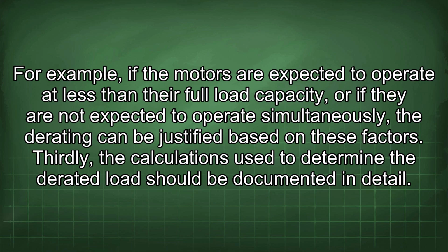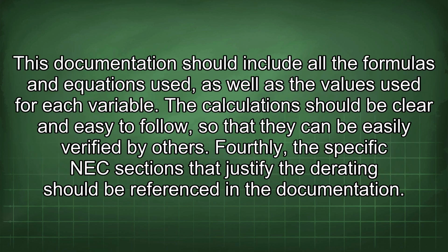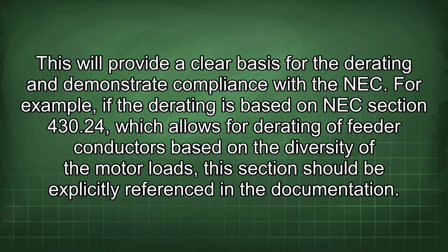Thirdly, the calculations used to determine the derated load should be documented in detail. This documentation should include all the formulas and equations used, as well as the values used for each variable. The calculations should be clear and easy to follow, so that they can be easily verified by others. Fourthly, the specific NEC sections that justify the derating should be referenced in the documentation. This will provide a clear basis for the derating and demonstrate compliance with the NEC.